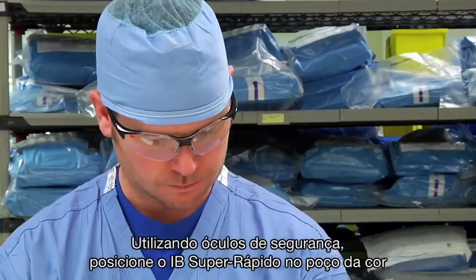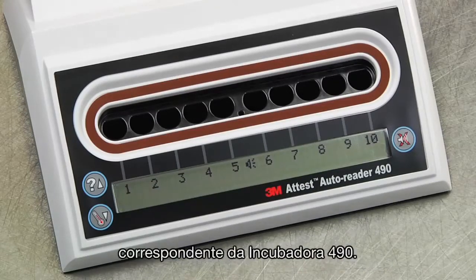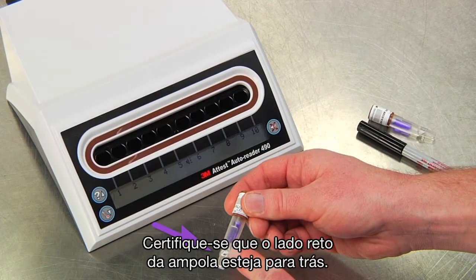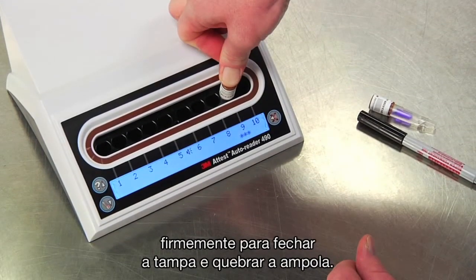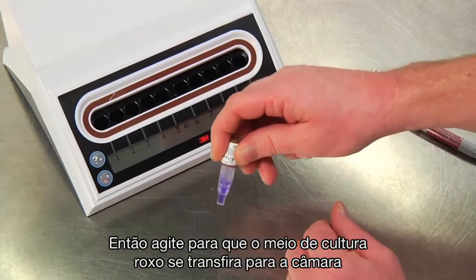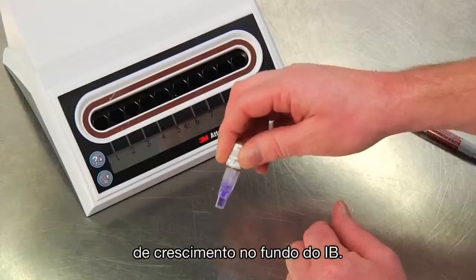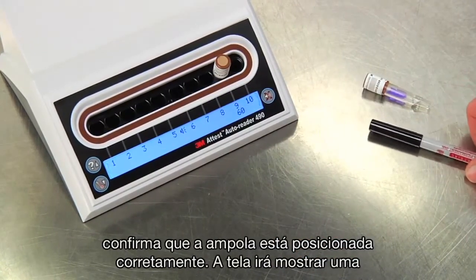Wearing safety glasses, place the Attest Super Rapid BI in a matching color-coded ATest Auto Reader 490 incubation well. Make sure the flat side of the vial faces the back of the Auto Reader. Press the cap of the Attest Super Rapid BI down firmly to close the cap and crush the glass ampule. Immediately remove the BI and visually verify that the glass ampule has been crushed. Then flick the vial to cause the purple growth media to flow to the growth chamber at the bottom of the vial. Return the activated BI to the incubation well and check the LCD panel to confirm that the vial is properly seated.